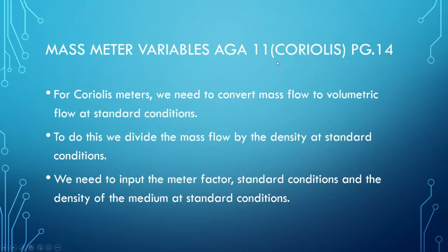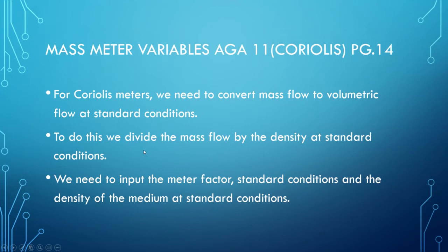AGA11 applies specifically to Coriolis meters. Coriolis meters can do volumetric flow, mass flow, density measurement, and temperature measurement. To use a Coriolis meter, we need to convert mass flow into volumetric flow at standard conditions by dividing mass flow by density. We also need to input the meter factor, the standard conditions, and the density of the medium at standard conditions.